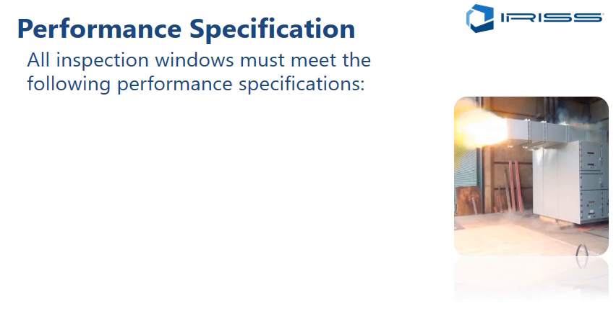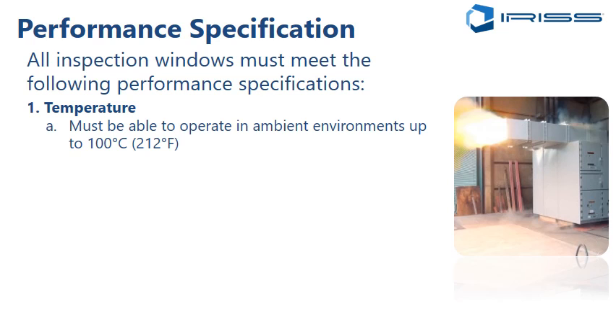Now, performance inspections is very, very important, and again, you need to consider this stuff. All inspection windows must meet the following performance specifications: Temperature, must be able to operate in ambient environments up to 100 Celsius. So that's the actual performance specifications of the lens. Now we know that I've said in previous slides they should be able to meet, be safe up to 250 degrees. That's fine, but we're actually talking about their physical operating temperatures now that they should be able to meet.